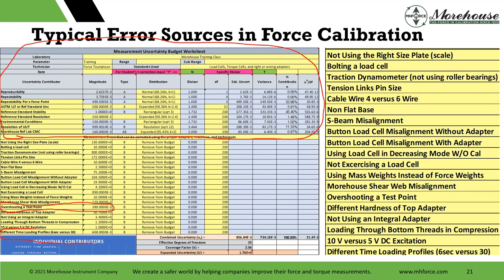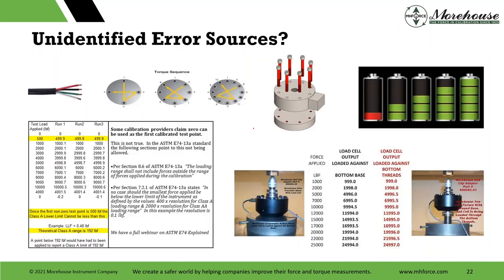Different timing profiles with automation. You set the timing. So basically you want to hold the force for 30 seconds and take multiple readings, not a problem. Other things are non-flat base. Other things are usually controlled with adapters, pinching, like tension, like pin size, process, like bolting a load cell. That's also adapters. Do you have bottom plates? Are you using the right ones? Roller bearings, cabling, all of that stuff. So there's lots of different error sources.